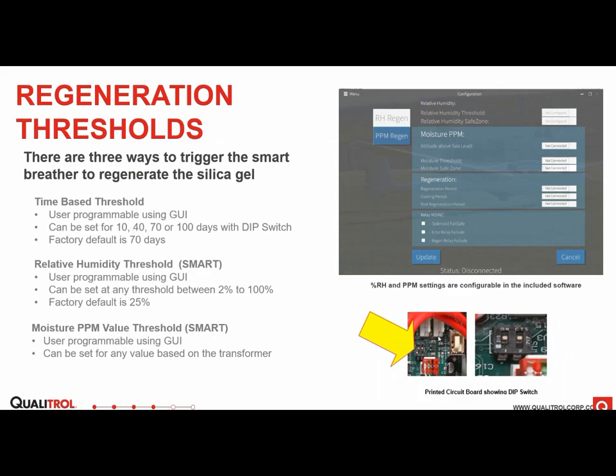The time-based mode is set with a dip switch on the PCB. So you flick these 2 switches and they'll give you either 10, 40, 70, or 100-day regen time. The RH humidity threshold, you can see here on the software, can be configured very easily through here. And then moisture ppm, which is a new feature, can also be configured through the software.